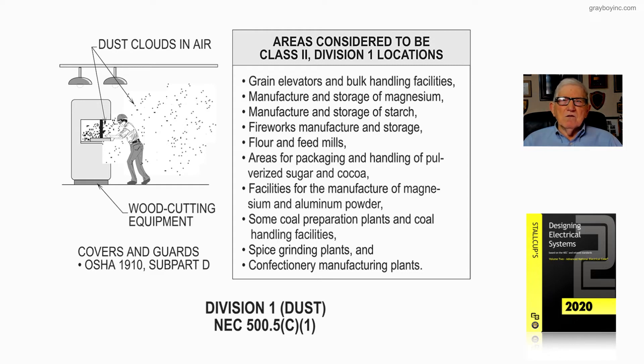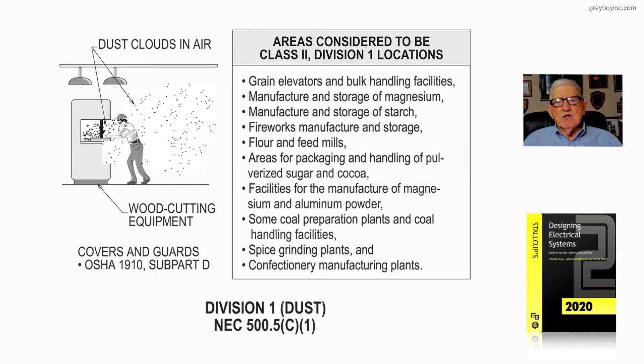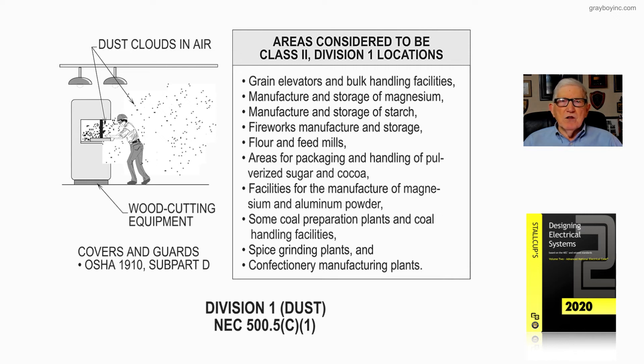If you have dust layers on the floor, on beams, ducts, and things like that, then you would reference NFPA 654 to determine when that becomes a problem. They have formulas in there to determine hazard levels. Dust that settles over an eighth of an inch puts you in an explosive range with dust gathering on equipment. NFPA 499 is used when dust collects on equipment; NFPA 654 is used when dust collects on steel beams, floors, and other areas — but not on equipment.